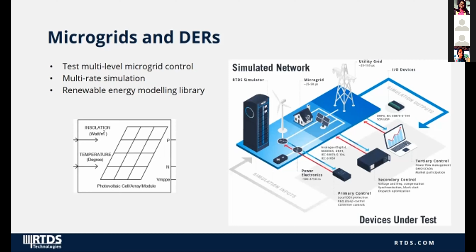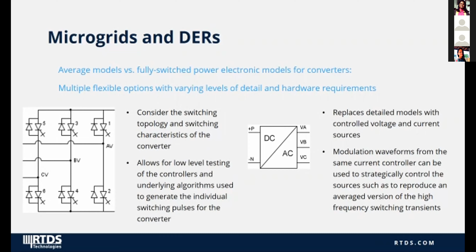Digital real-time simulators also have options for simulating power electronics via average value models instead of full switch simulation models. Average models are essentially controlled voltage and current sources which sit in the main simulation time step. They are able to accurately represent the real and reactive power profile of the inverter both in steady state and transient conditions, but they don't represent the high frequency switching dynamics.